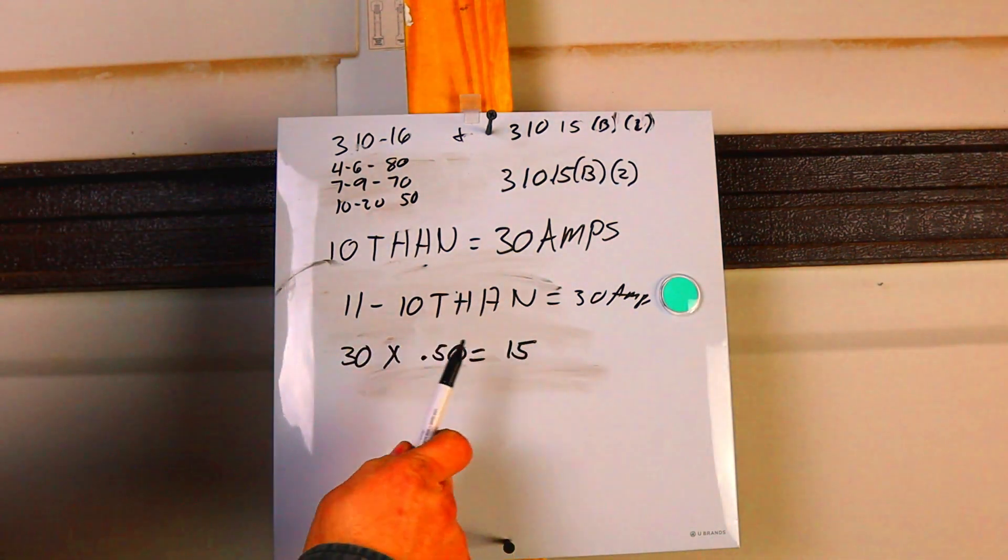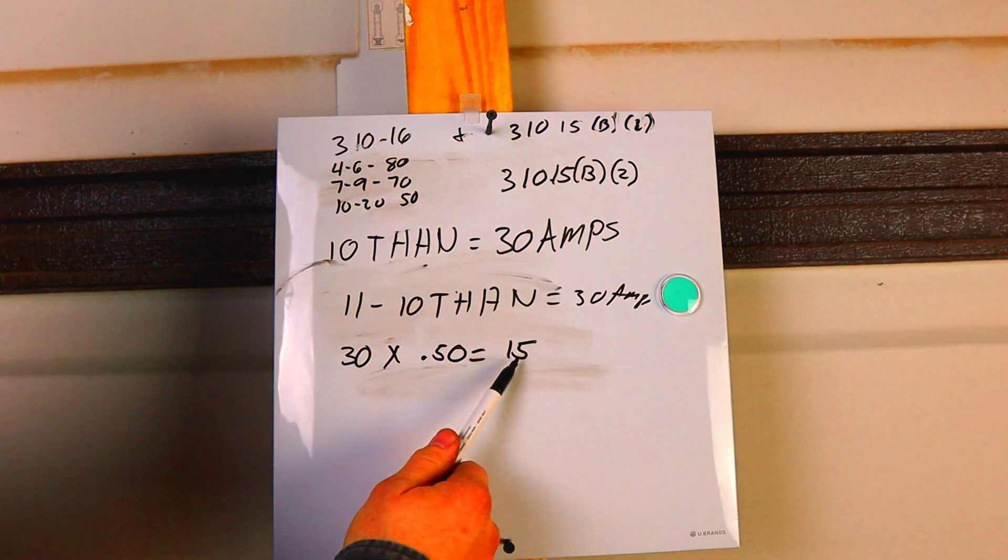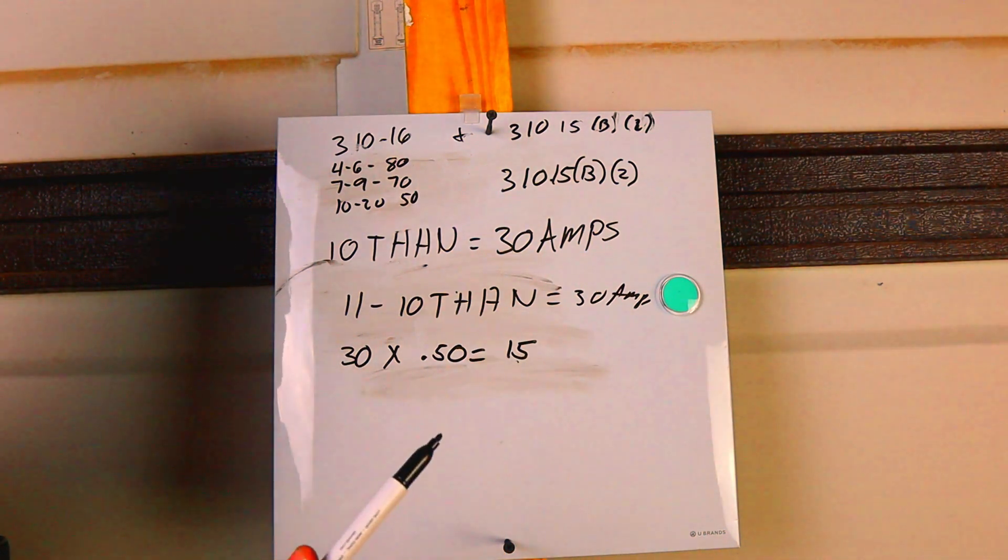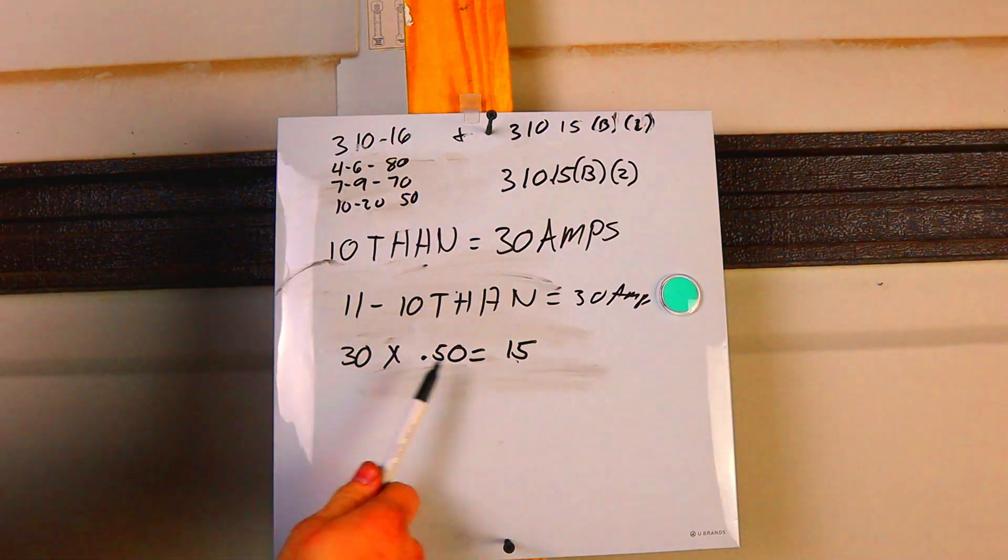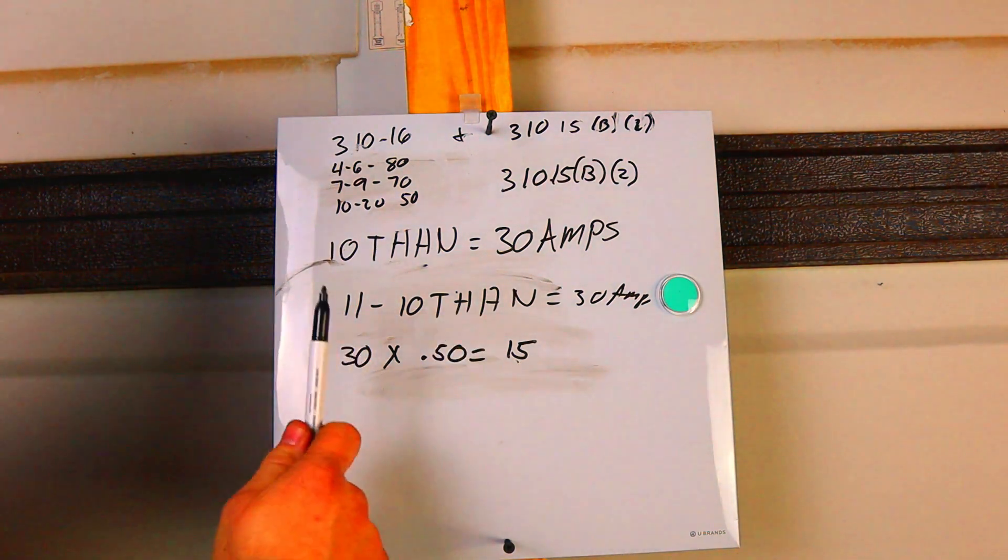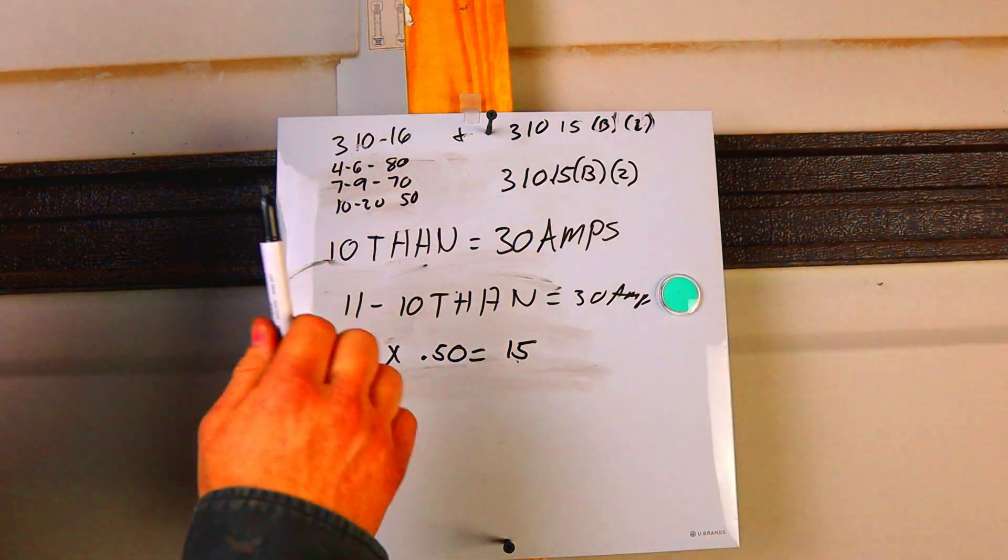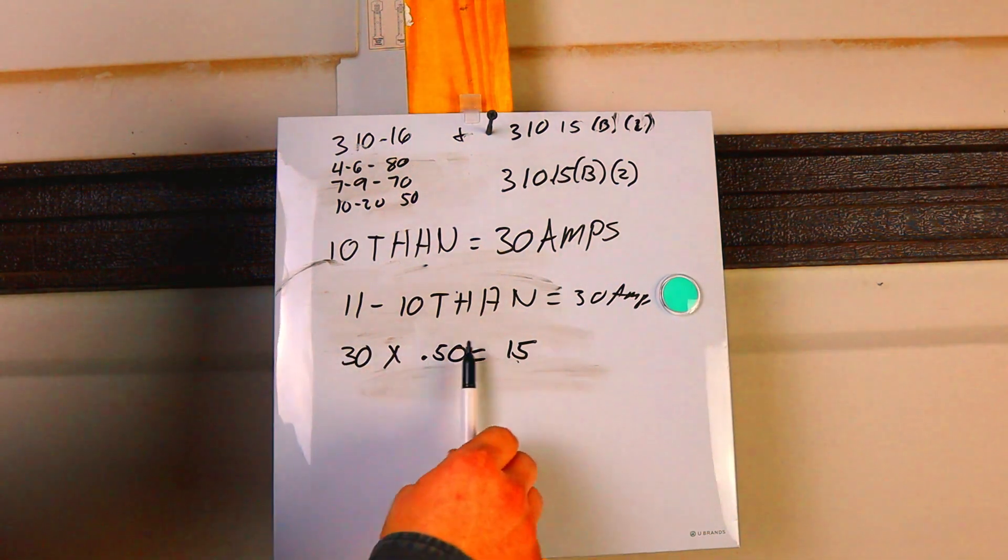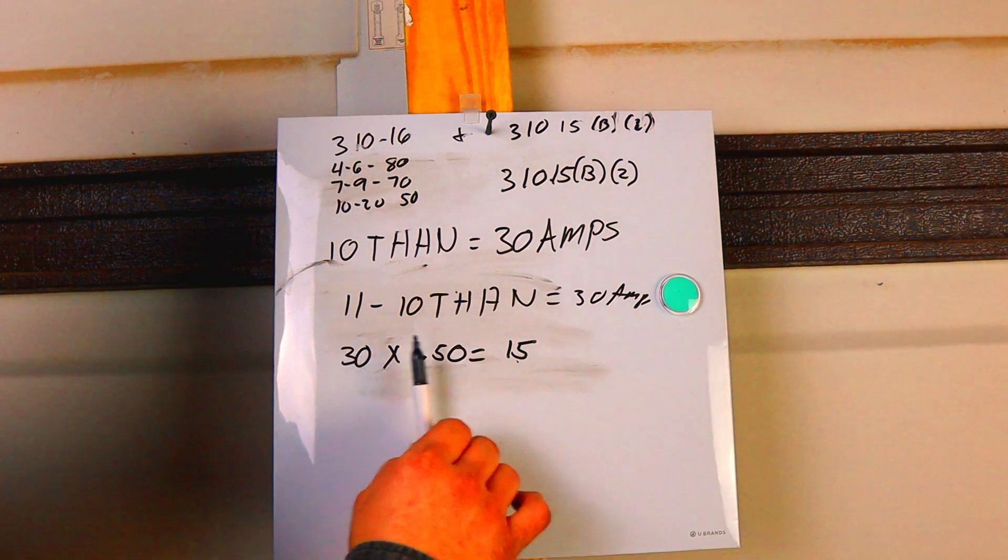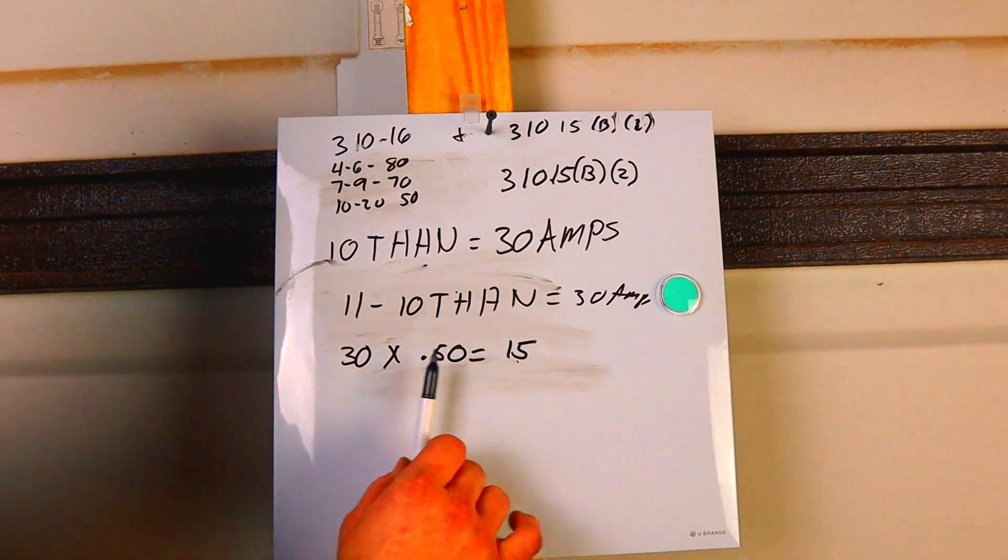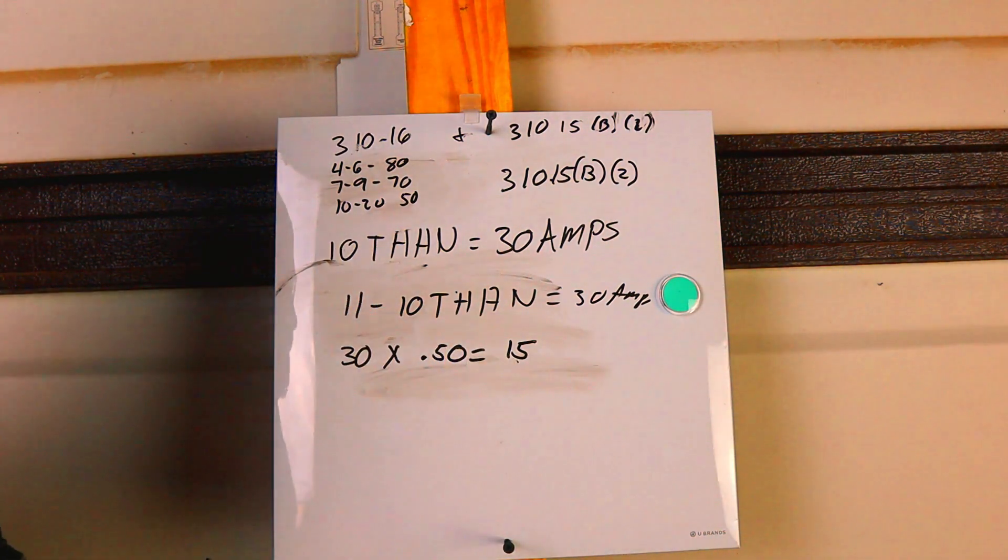So now if we need 30 amps over there, we're only going to be able to get 15. So that right there tells you that you're going to have to bump up your wire size to whatever it takes to get to 30. Now, we're not going to go into that right now, but I'm just showing you guys basically what you need to do. You're only going to get 15 amps if you have 11 wires in a conduit. So I hope that clarified a few things and it made you understand that you can't just put X amount of wires in a conduit.